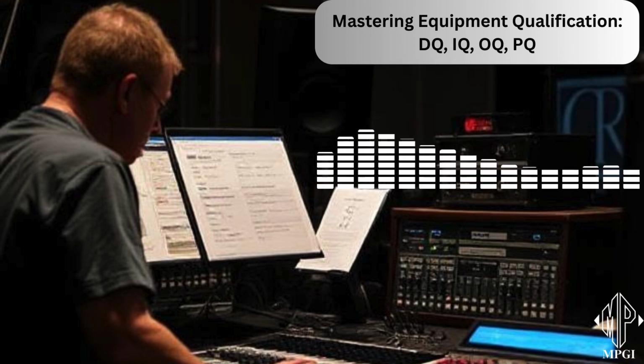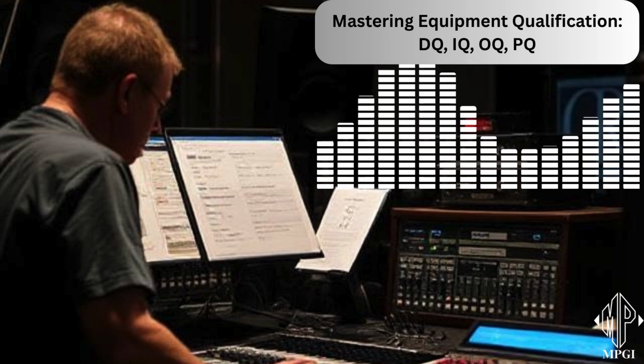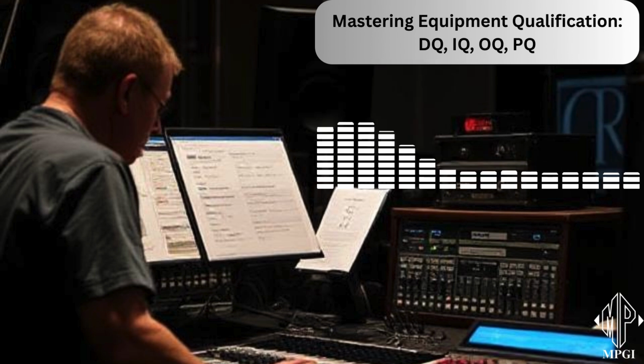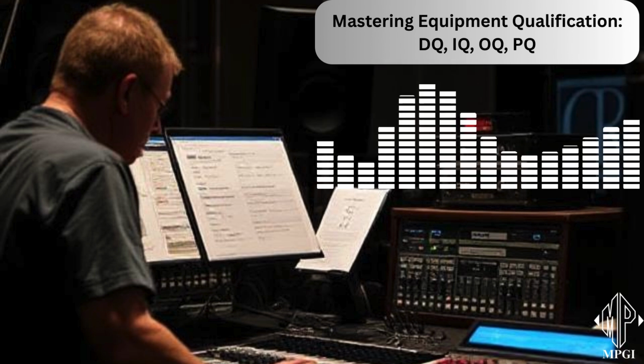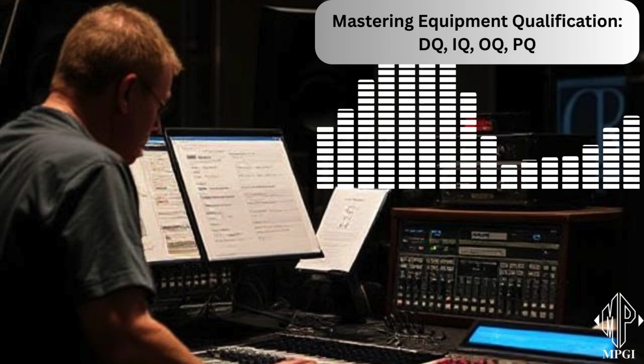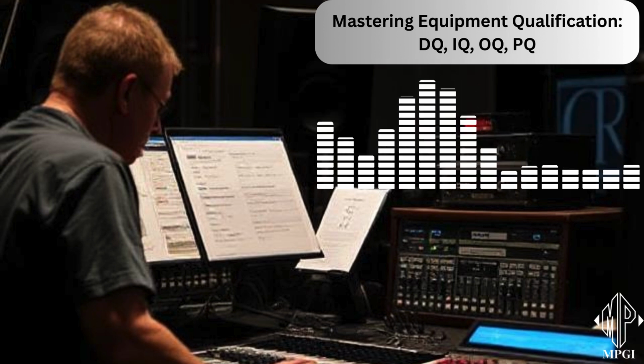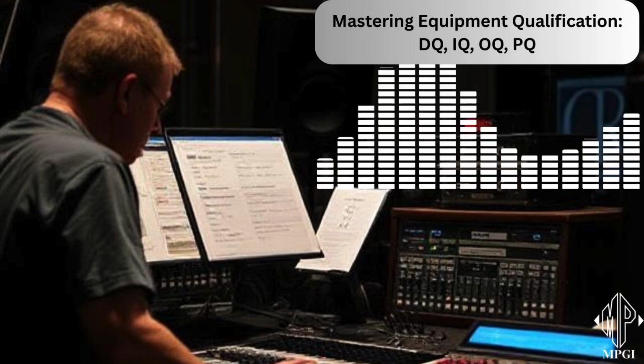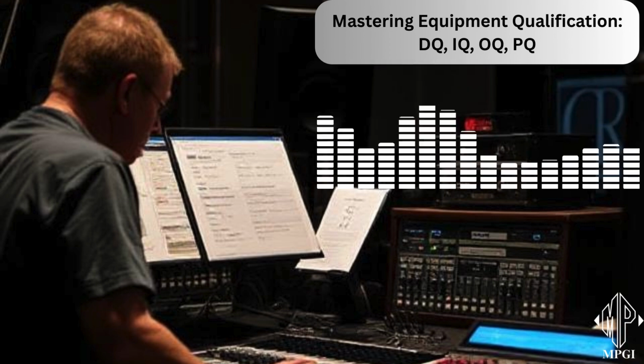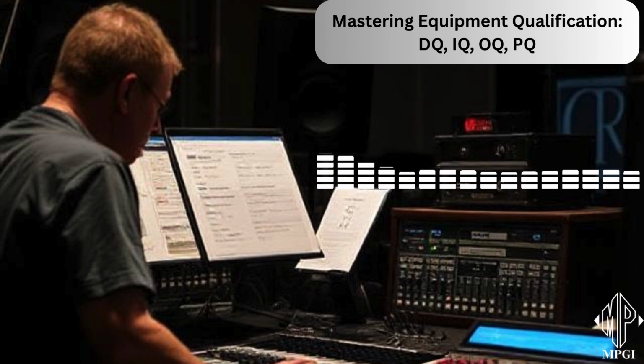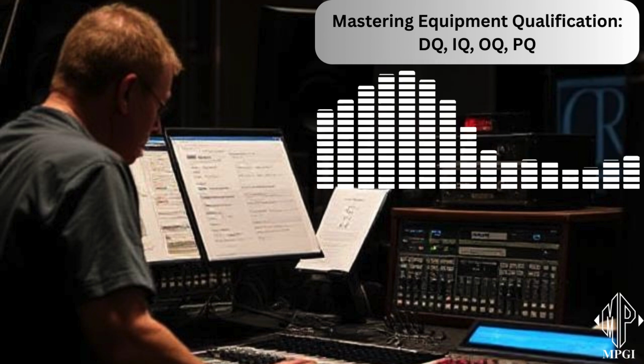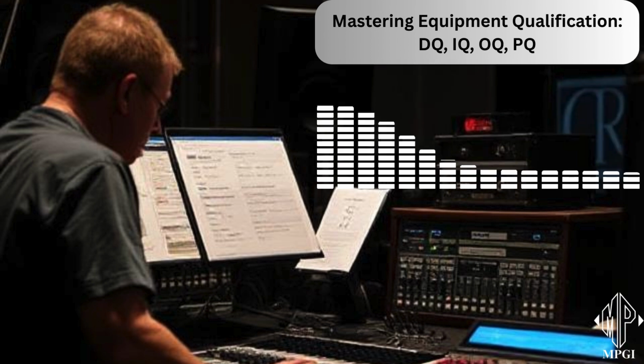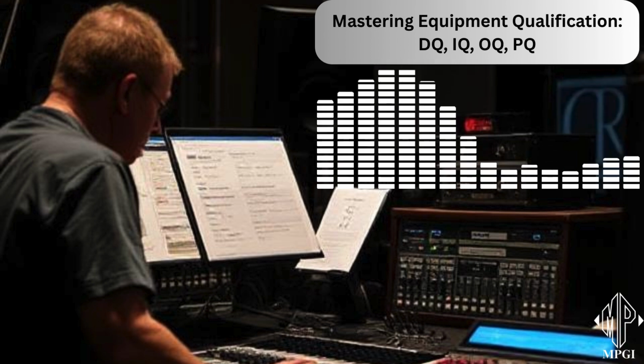Exactly. They also make sure it's in the right spot and that all the utility connections like electricity, water, air, whatever it needs, are all correctly hooked up and functioning. So they're not just making sure it's plugged in, but that the right voltage, the right kind of water, everything is perfect. All right, all the supporting equipment, software, firmware, everything gets checked. And then they make sure they have all the manuals, certifications, calibration records for any tools used. Plus, they give the equipment a thorough look over for any damage that might have happened during shipping. They're being super meticulous here, leaving nothing to chance.